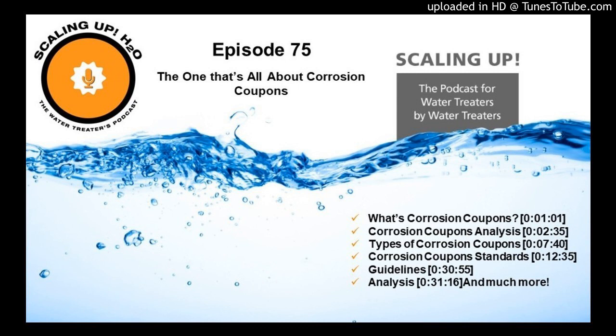I'm going to replace those two that I just took out with, again, mild steel and copper. And then the next 30 days, I'm going to come and remove that set that I put in originally, but now it's been in the system for 60 days, and replace those. And now every 30 days, I have 60-day results. So that gets me a little bit more accurate, and I get a whole bunch of data points with that. Again, the more accurate data points that we get within the system, the better we can use these corrosion coupons to change our program, or at least verify that our program is working properly.